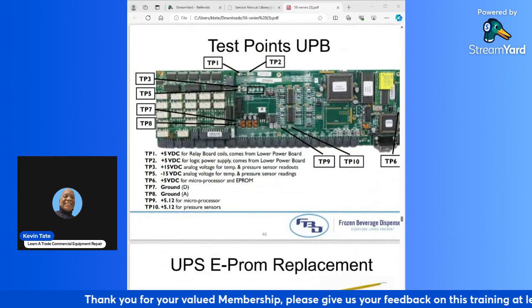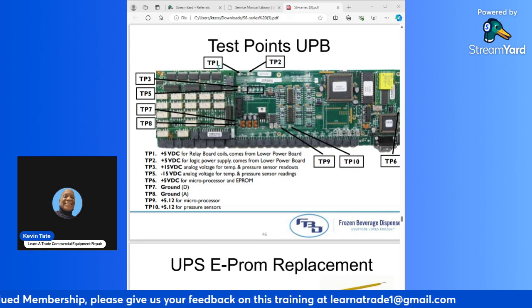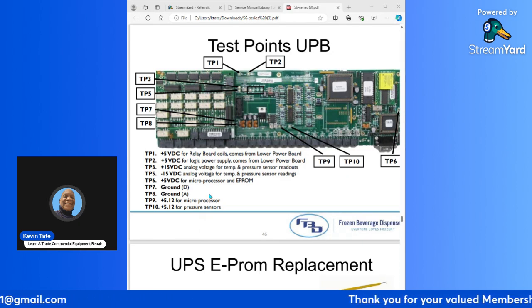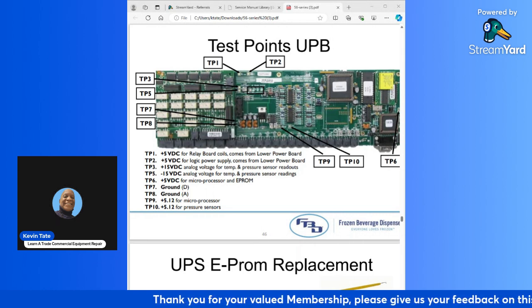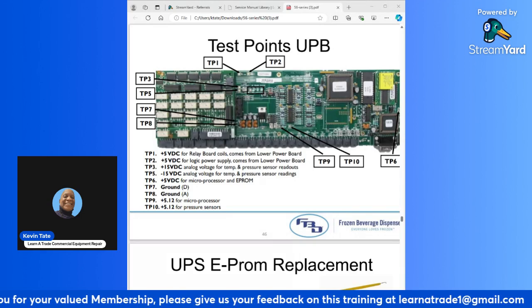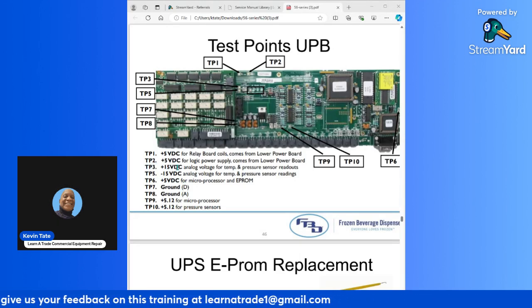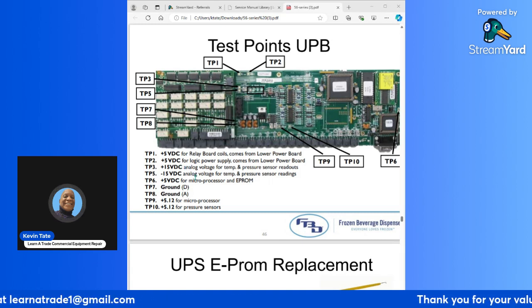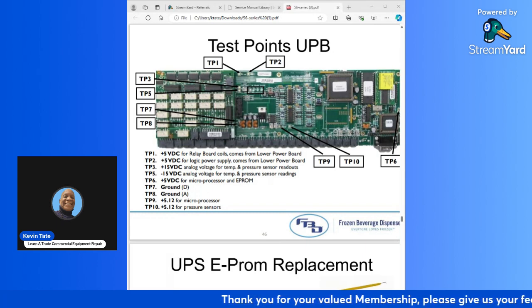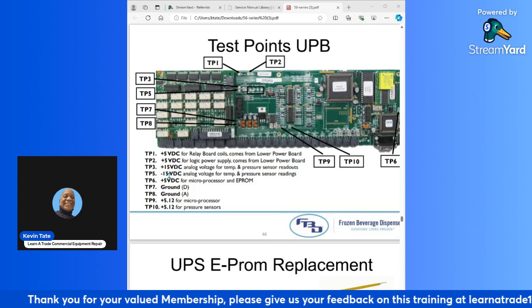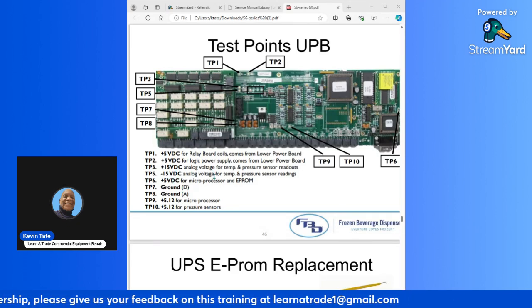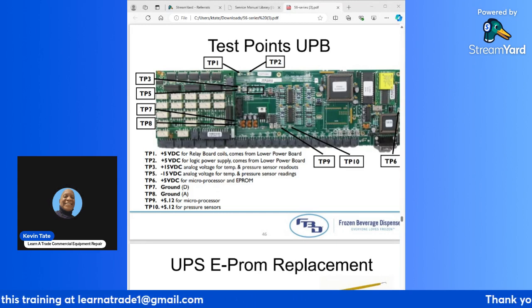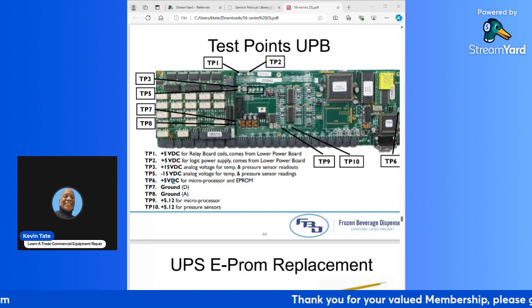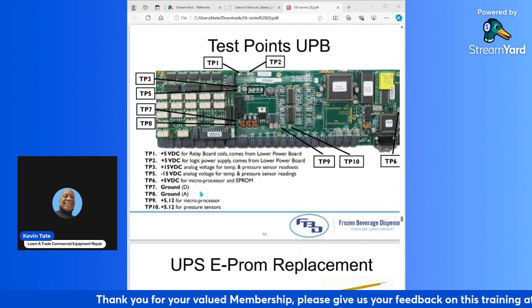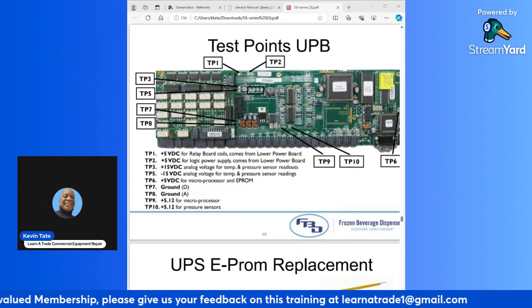Test points for your upper board. We're going to start up here with test point 1, TP1. TP1 is your positive 5 volts DC for relay board coils, comes from lower power board. Test point 2, positive 5 volts DC for logic power supply, comes from lower power board. TP3 is a plus 15 volts DC analog voltage for temperature and pressure sensor readouts. TP5 is a negative 15 volts DC for your analog voltage for temperature and pressure sensor readouts.